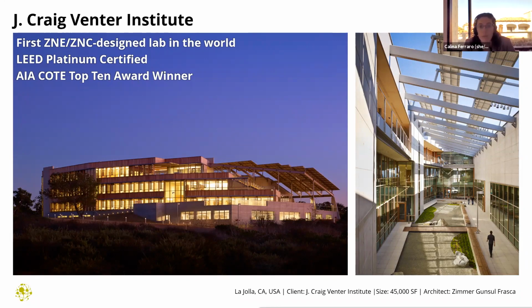You can see it has a large PV array, and it also incorporates some of that thermal storage we talked about. There are two 25,000 gallon water tanks embedded under the parking garage below the building. During the day when we're cooling, we take the heat collected in the water and push that warm water into these tanks. Then in the evening, because we're in San Diego, we tend to have warm days and cool nights, so when we need that for heating, we pull that heat back out and use it to heat the building.